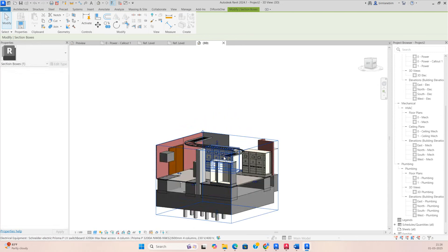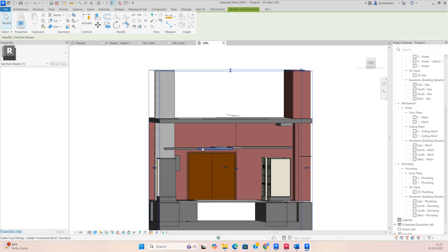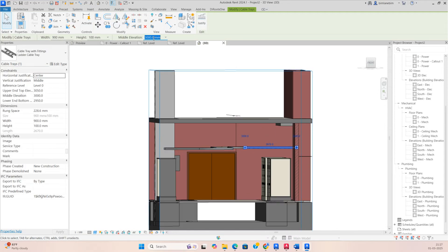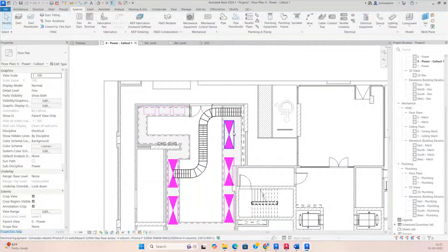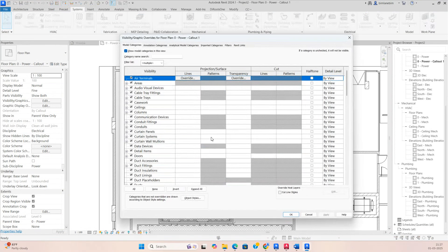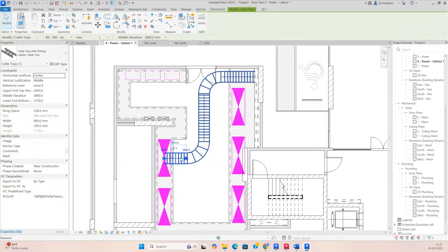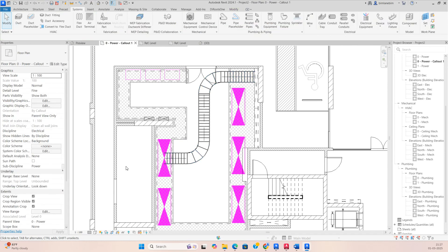You can select the cable ladder and see how it is running. If you need more elevation, select the cable and change the elevation — for example 3500 or 3800mm. You can also assign filters; I'm making a service type called 'Cable Ladder 1' for this cable ladder.